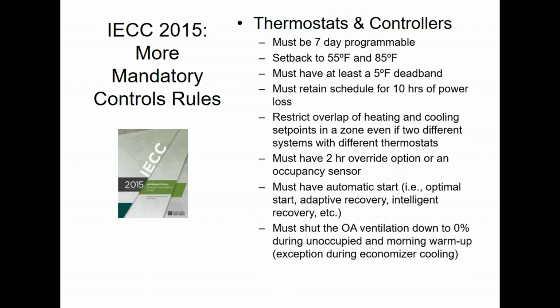You have to have an interlock between the thermostat or the DDC system to the ventilation system. I guess technically you don't have to have a thermostat, but you could have a second device on the wall next to the thermostat, but that would be kind of silly. Just get a thermostat that has an extra output that does all this for you. But the ventilation damper needs to remain closed until the occupied period begins. Like I said, if the schedule begins at 8 a.m., you leave the damper shut until 8 a.m. Even though you may want to turn heating and cooling on earlier than that to start warming up the building, you leave the damper shut while you're doing the warm-up period or cool-down period, whichever you may need.